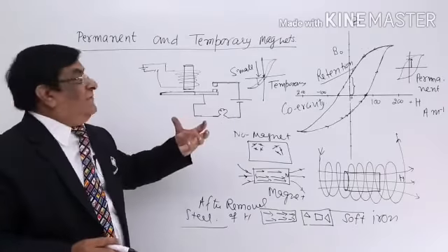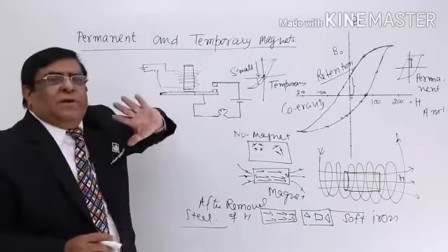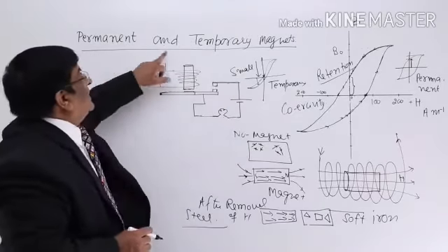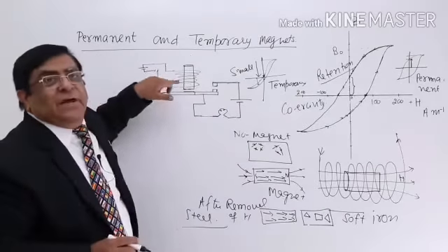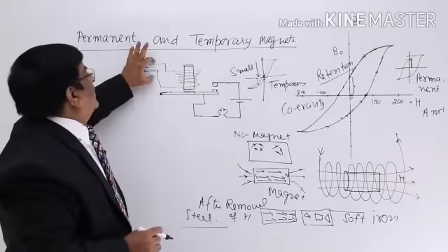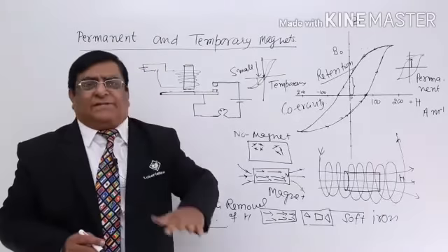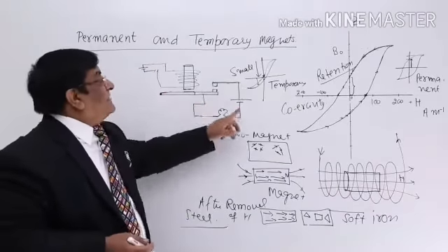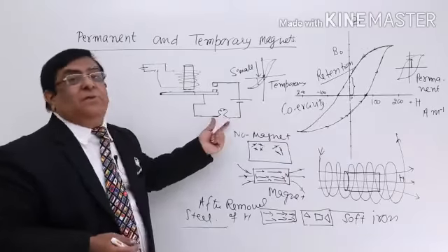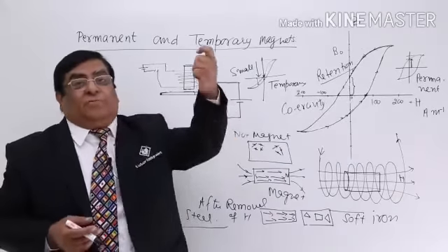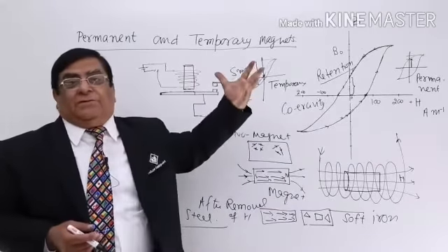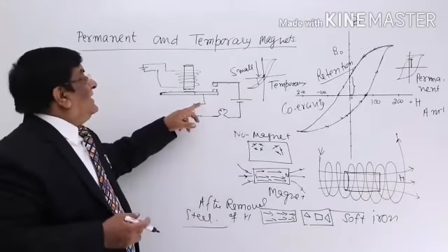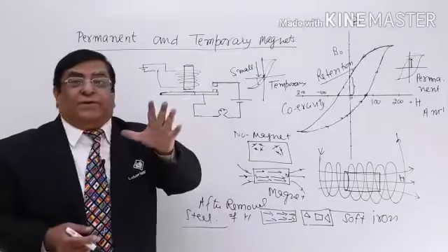What is the benefit of this? When you study machines and controls, this is known as a relay circuit. A relay circuit is a very small circuit operating on a 2-volt battery, like our remote. This is a power circuit. This motor is a 175 horsepower motor which runs the plant, and it takes so much heavy current that I would not like to operate its switch directly.